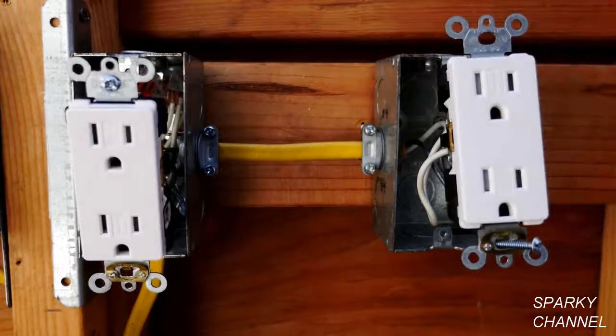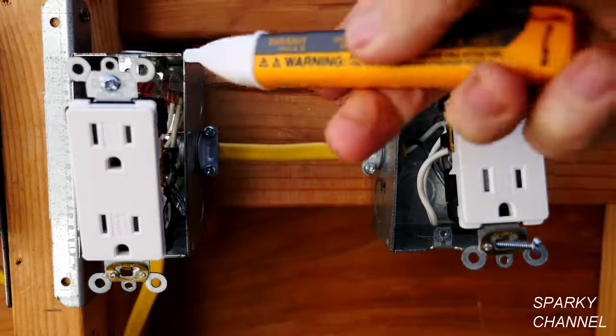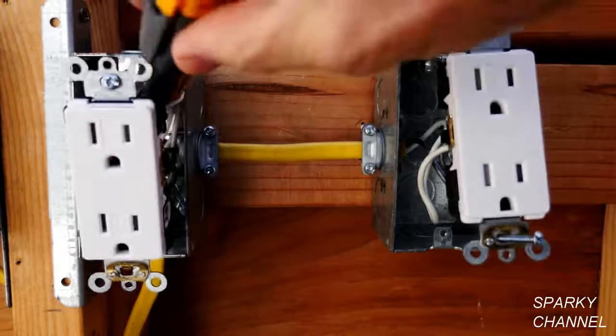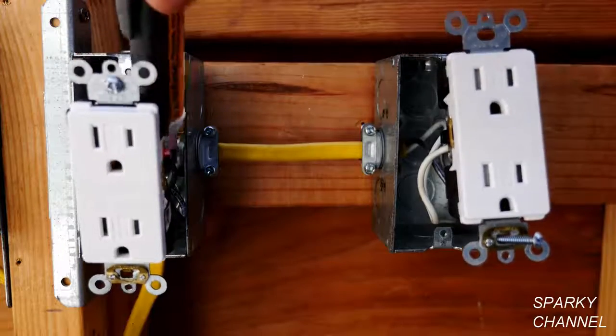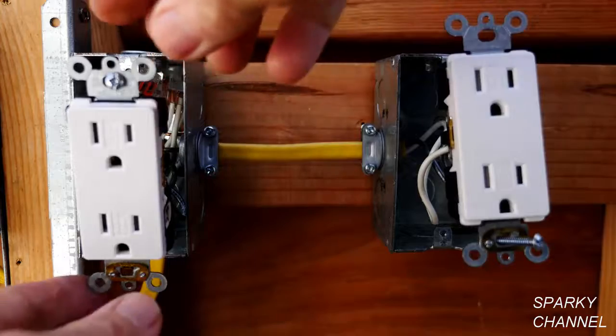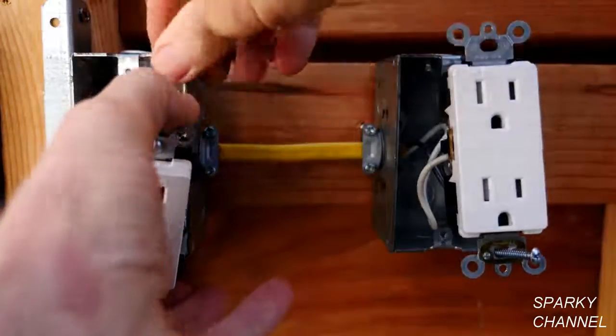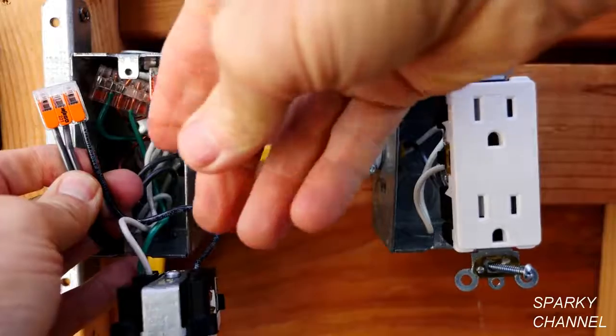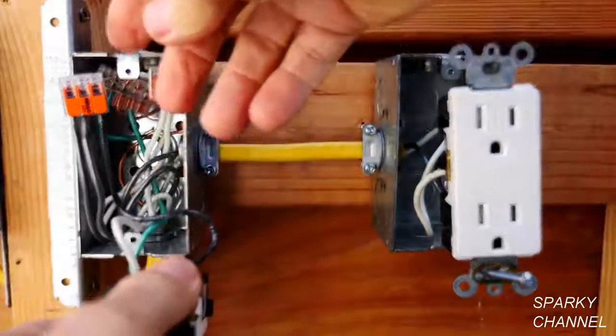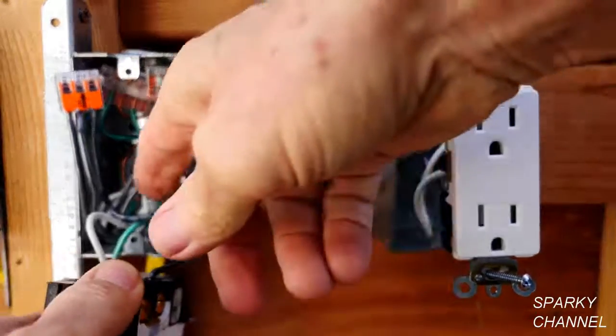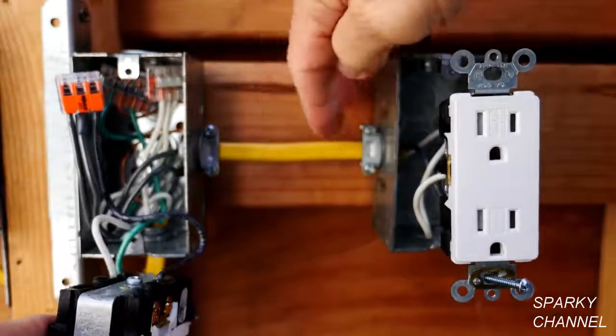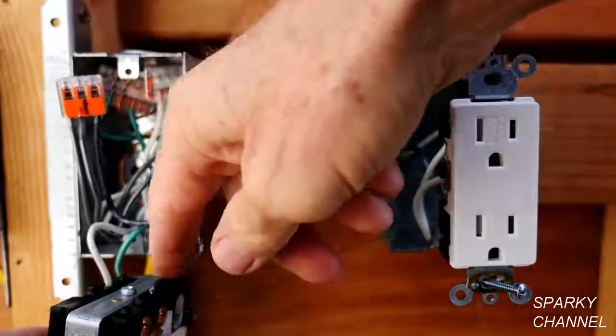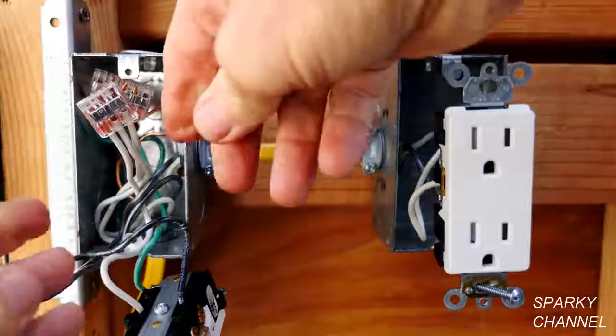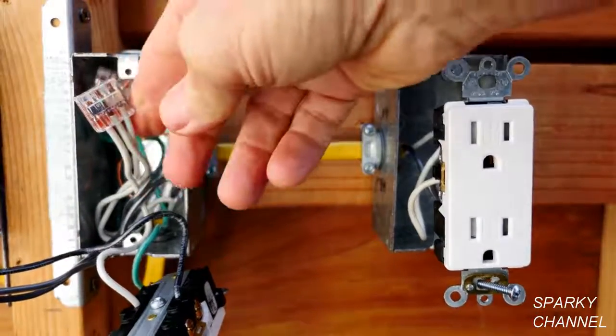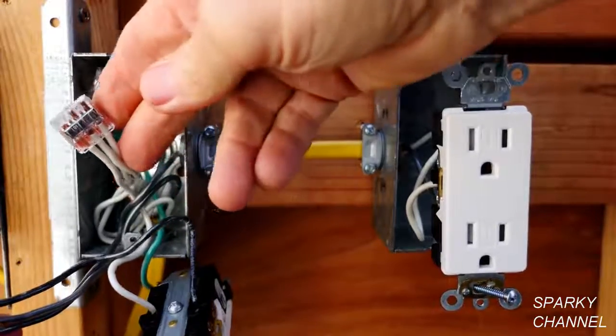I've now loosened up this receptacle and I'm going to test with my voltage detector back in the back of the box, make sure there's no live wires at all in this box. There are none. And so now let's see what's going on with the ground. Here we have the hot wires. You see there's three hot wires, one coming from the power source, one going over to the next receptacle, and one going to the receptacle, so that's proper. Here we have the neutral. This was the same situation with three, so that's proper.